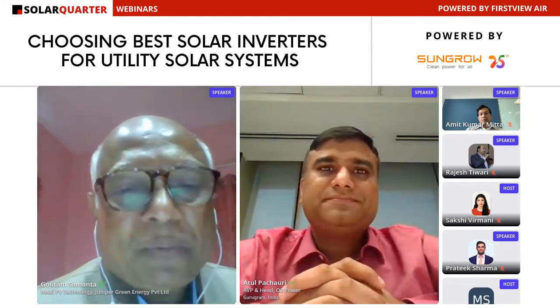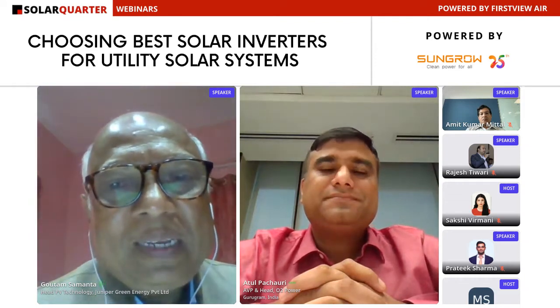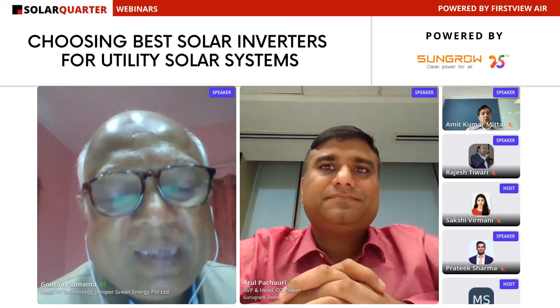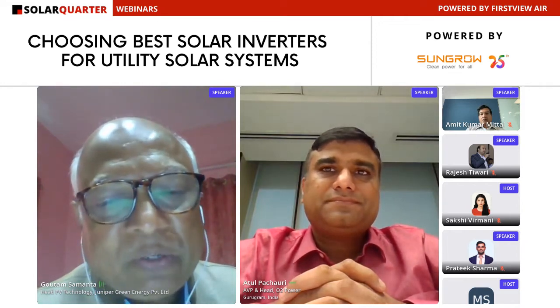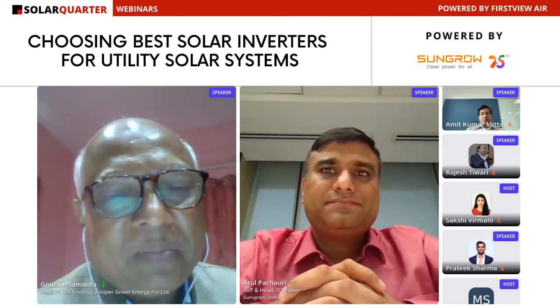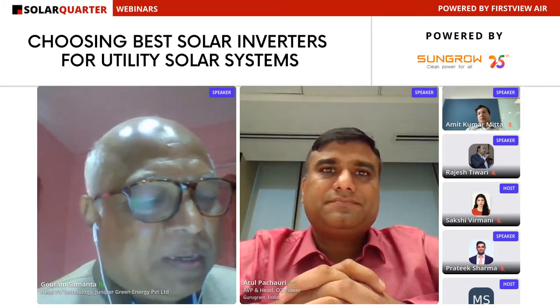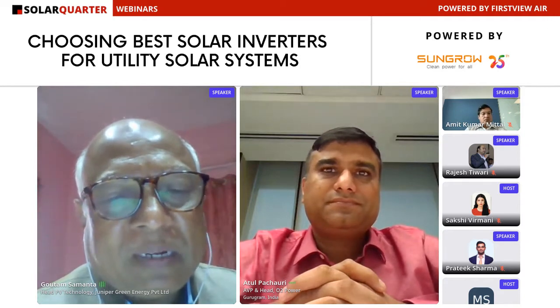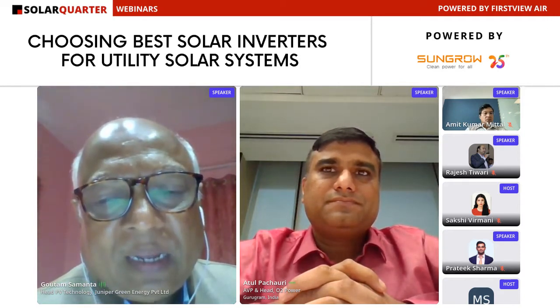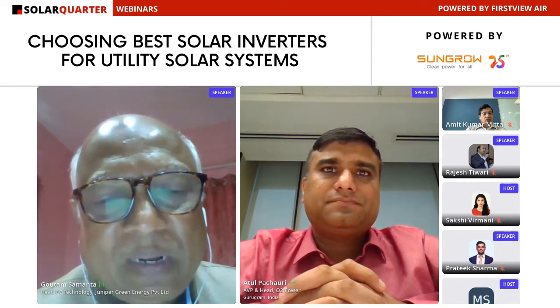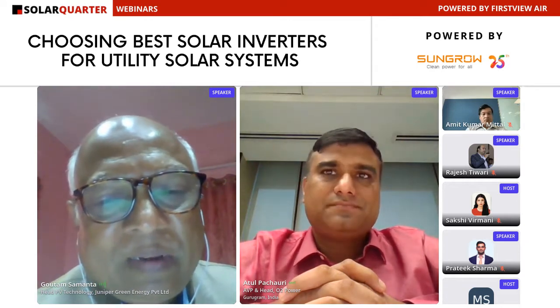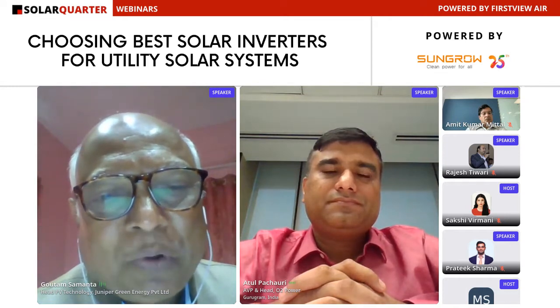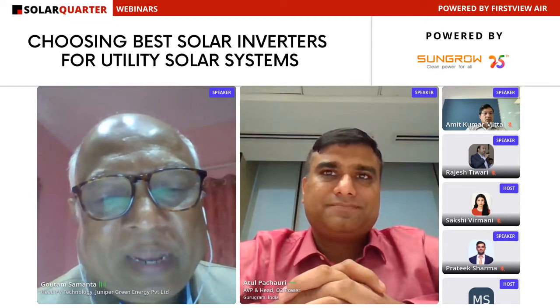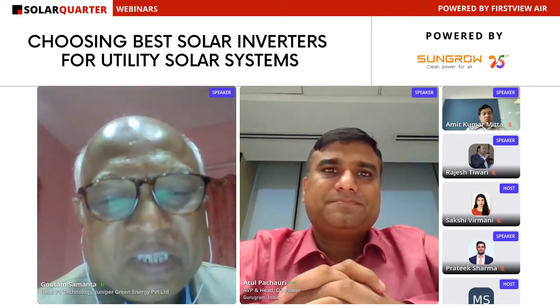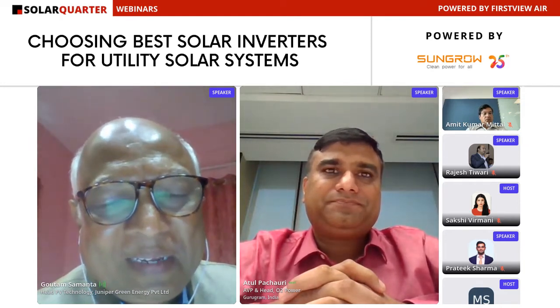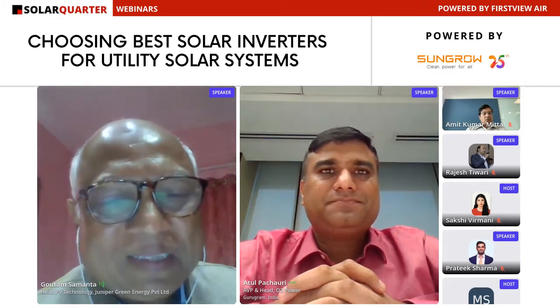Absolutely, I think you're on the right track from the operation and maintenance point of view. Generation is very important, with less downtime. In troubleshooting, if a central inverter is down for a couple of hours, sometimes spares aren't available, maybe fuses, small things, or a card, not at the initial stage but after a few years. But with string inverters, several are available quickly in stores, and you can replace them within a couple of hours. With a dashboard you can monitor and find the exact location where you need to act. So from the generation and revenue point of view, yes, you are on the right side, wanting less downtime. We will discuss more on that.